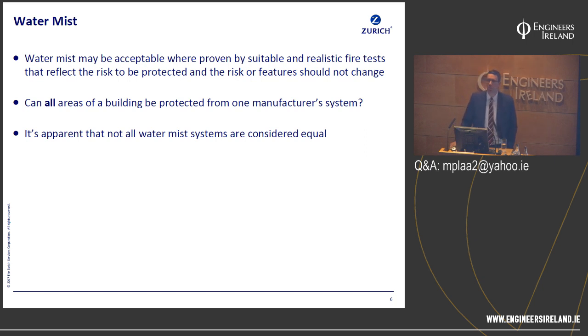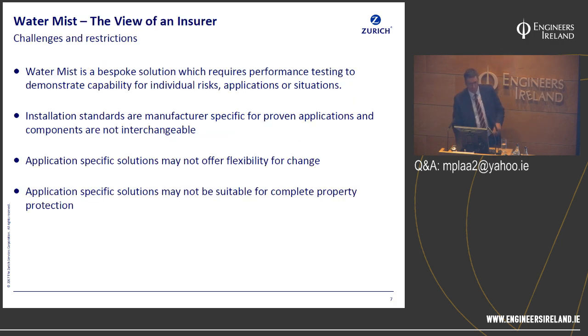And not all water mist systems are equal. It is a very mixed bag. There are some very good manufacturers and suppliers out there, and there are some very poor ones. It's very much a case of the good, the bad and the ugly. So it is a bespoke solution, and it's important to understand that water mist needs representative fire test data for the application in which it's being used. It's common for me to be given fire test data for one application where genuinely the system has gone through robust testing by an independent lab, and then it's being used for something else, hoping that we wouldn't recognise that, or hoping that we wouldn't be caught out by that. So it's really important that if it's tested for A, it's actually used in A and not used in B.